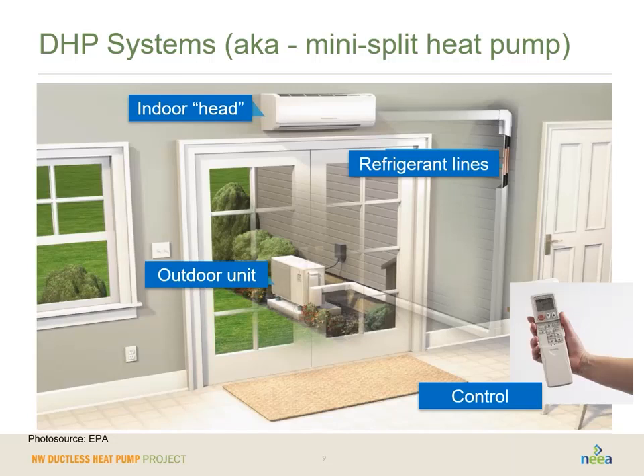The refrigerant lines connect them, and then the indoor head has a high efficiency fan that's actually able to modulate its speed according to the needs of the house. This is all managed by the controller, sometimes referred to as the wand, the one that's pictured here. Now, the wand is kind of a glorified remote control that's really designed to control your ductless heat pump. For some of your customers who prefer the wall-mounted thermostat that they're used to for their other heating systems, most manufacturers do make a wall-mounted controller as well, and so that is an option, and we'll talk a little bit about that a little later.